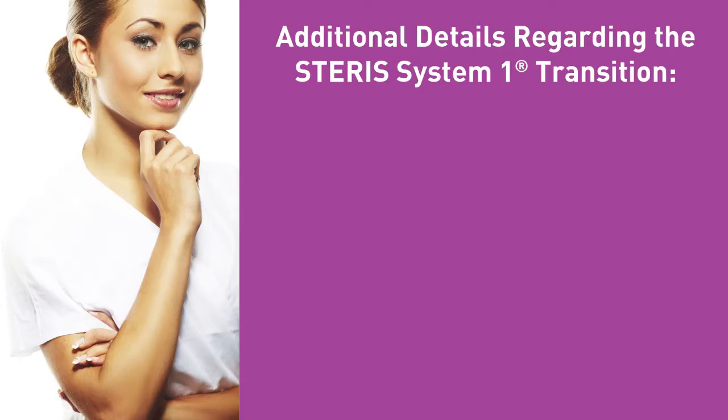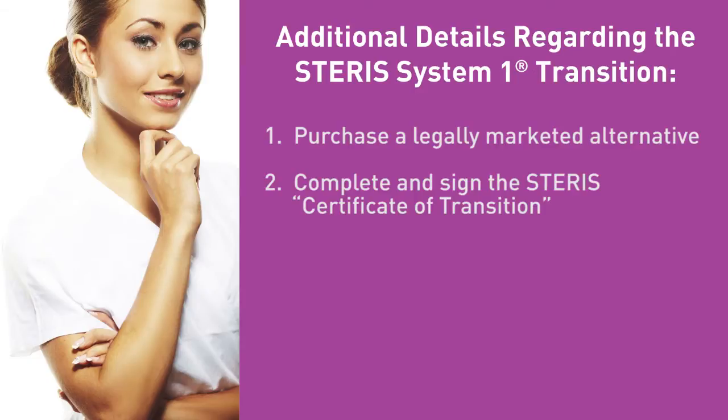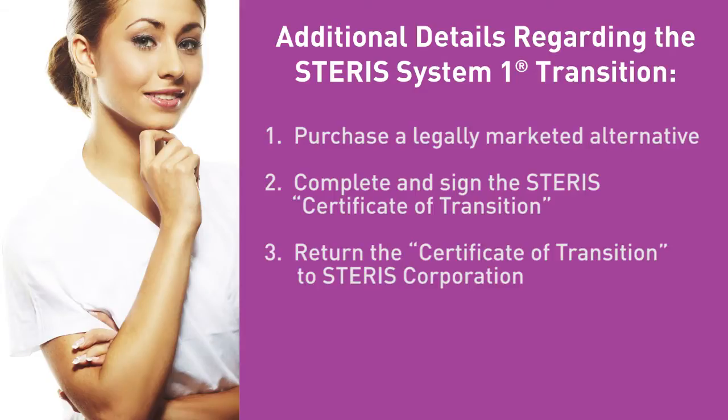By now you have probably received a letter from Steris dated December 22nd requesting that if you intend to continue purchasing S20 Sterilant, you do the following: 1) purchase a legally marketed alternative, 2) complete and sign the Steris certificate of transition, and 3) return the certificate of transition to Steris Corporation. Steris will discontinue support for SS1 customers who do not provide them a completed certificate of transition.